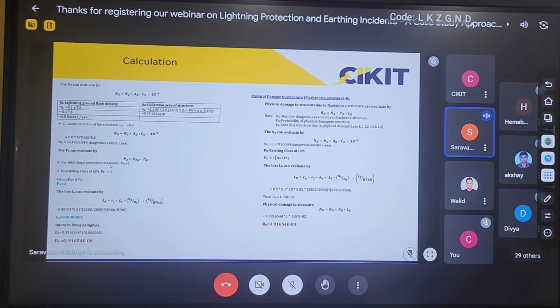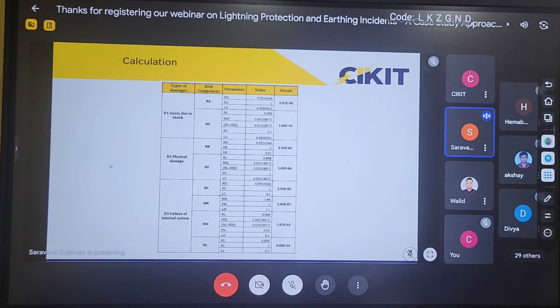After making these modifications, we have to note down what modifications we have made. We have considered an automatic fire fighting system. We have considered a lightning protection system at level 1. We have considered surge protection devices at level 1. We have provided additional protection measures of electrical insulation for physical restrictions. If I provide physical restrictions, the value will drop to 0. By providing these measures, we bring down the risk due to lightning in the form of step and touch voltages. So this is how we have to perform the calculation, and our ultimate aim is to bring down the value of R lower than RT.